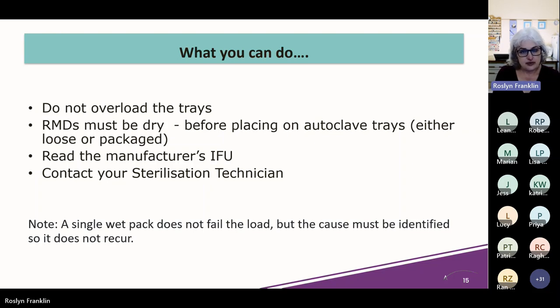So if that happens, have a look, go back. Okay, have I overloaded the trays? The manufacturer's instructions will tell you what weight of instruments you can put in if you're not sure. If you're confident you didn't overload, there is possibly another cause, so look at your instructions and see what it says in that troubleshooting section.